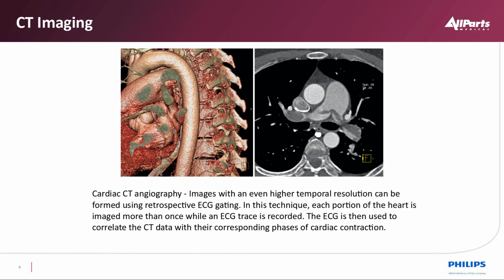Also, with regards to CT, if we rotate the gantry very quickly and we gate on a certain function within the heart, we can essentially have gated data sets. It may take a few rotations to build a complete data set enough to do recon, which would be at least a minimum of 180 degrees' worth of data. But at different phases of the heart, we can grab 20, 30, 40 degrees, then overlap the next one with the next one at a given location, and then have enough built up for 180 degrees' worth of data set to back project an image.